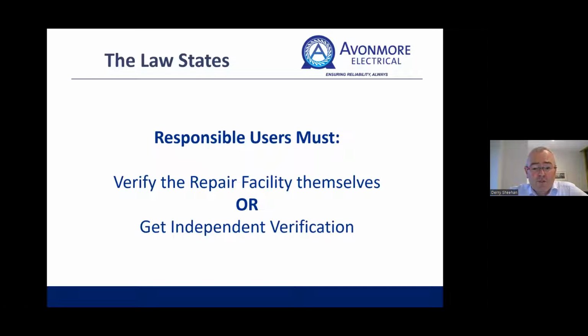Responsible users must follow the standards - I'm talking about 60079, the series of standards for EX equipment, with various sections after that. The repair standard is -19, and the inspection one is -14. Responsible users must verify the repair facility themselves or get an independent verification. That's part of the user's responsibilities.